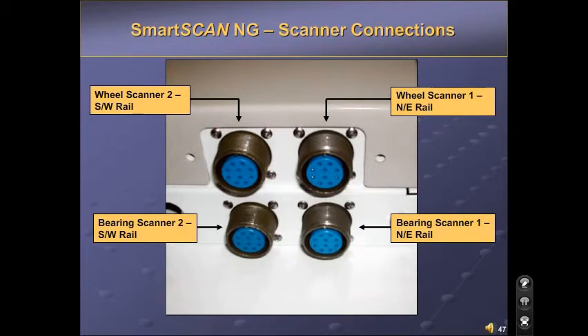The four scanner connections are identical, so it's important to make sure that you plug your scanners into the correct connector. The easiest way to tell if they are not in the correct position is during AutoCal. When the laptop says it found heat on a scanner, make sure the label in AutoCal matches the scanner on the track with the heat source on it.